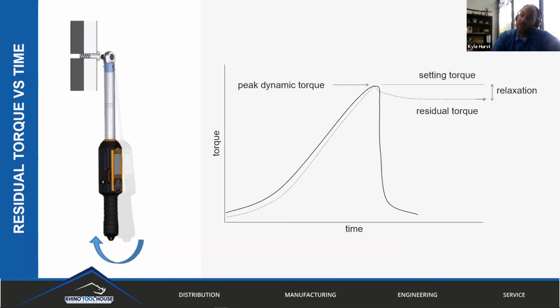But the second part is you are typically measuring other transducers, and so the numbers should line up, and they normally do. So even with your known master, the known good, if I put the tool to 50 and I know this tool was working at some level, and the tool says 50 and the transducer says 40, and I've adjusted the tool and done these things and they just never really line up...